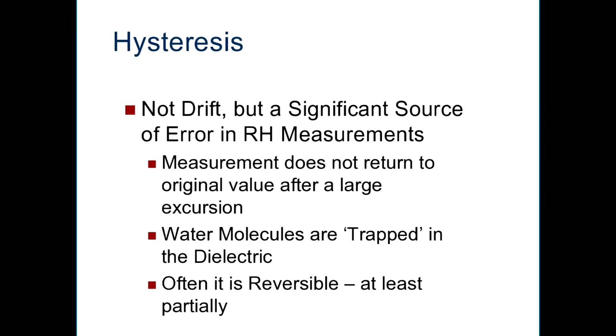We'll talk about another characteristic of most RH measurement systems, particularly capacitive RH measuring systems, and this is hysteresis. This is not really a drift, but it's still a very significant source of RH measurement error. Hysteresis is when a measurement does not return to an original value after a large excursion. Water molecules are effectively trapped within the dielectric. Often it's reversible, at least partially, but it may take a substantial period of time, sometimes days, to recover. Heating the RH sensor can actually help reverse it much quicker.